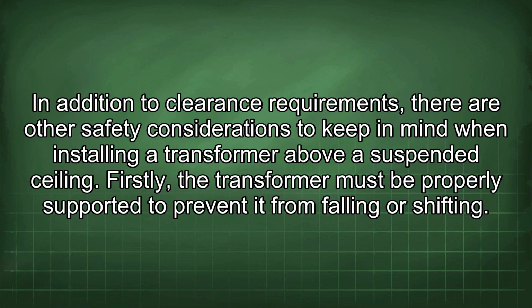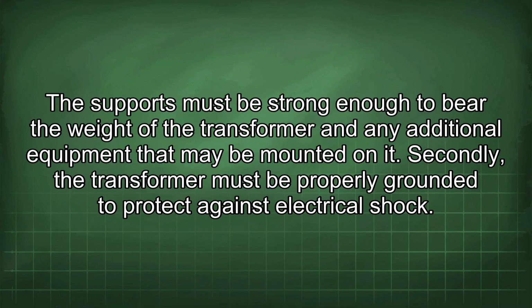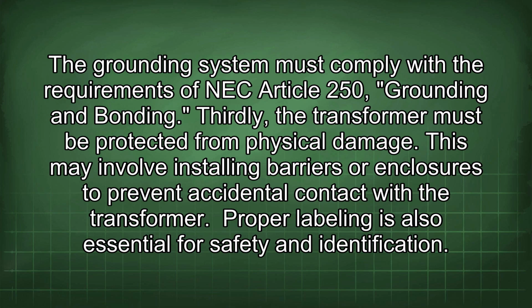above a suspended ceiling. Firstly, the transformer must be properly supported to prevent it from falling or shifting. The supports must be strong enough to bear the weight of the transformer and any additional equipment that may be mounted on it. Secondly, the transformer must be properly grounded to protect against electrical shock. The grounding system must comply with the requirements of NEC Article 250, grounding and bonding. Thirdly, the transformer must be protected from physical damage. This may involve installing barriers or enclosures to prevent accidental contact with the transformer.